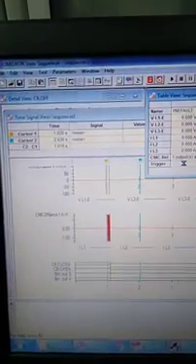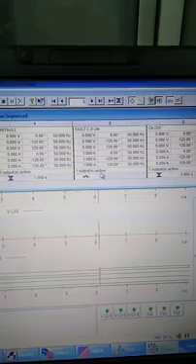In this video clip, I will show you how to test the 7SA auto recloser function for a distance relay. First, we have to set the state sequencer. In the case we have here, we have a pre-fault state with 0 voltage and 0 current, with activation of a binary output to indicate CB closed. Then we will go to fault: fault, CB on, and after that CB tripped, and after that CB reclosed.